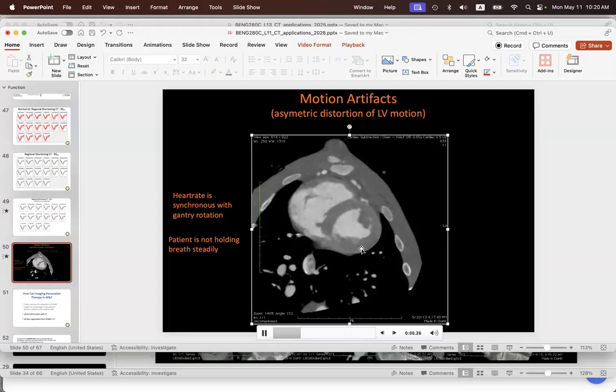So you can see there's an interesting artifact in the motion of the wall, in that it looks like there's a double wall on occasion, and it's almost like it's clicking around the heart. So it's click, click, click, click, goes around, and that essentially is sensitivity to motion artifact depending on the gantry angle.